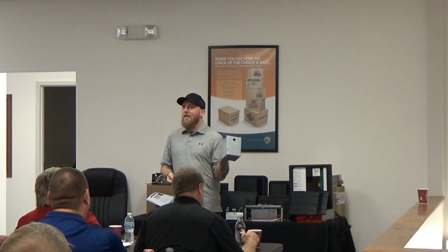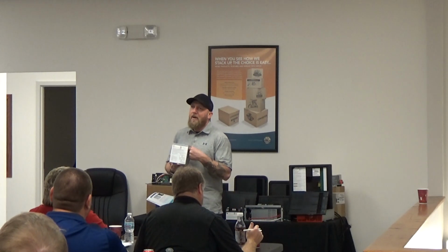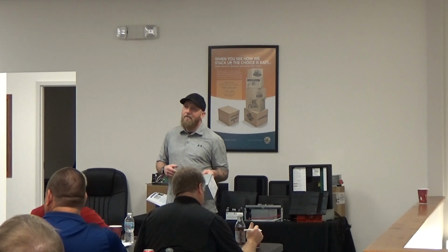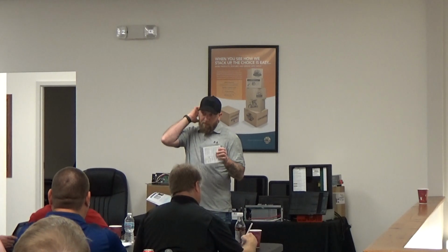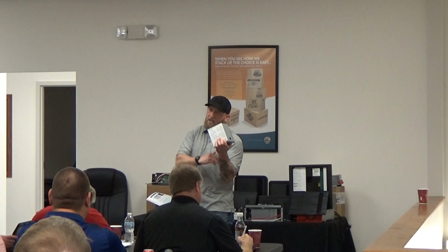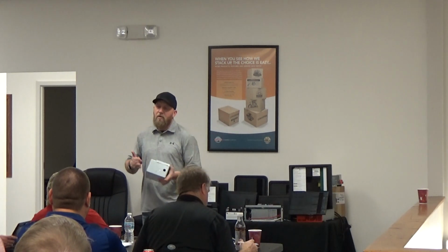Did you say yesterday there's not really anything that could go wrong with this? No, he didn't say that—there are things that can go wrong with it. It has an AC fuse on the timing board, so if you put too high a voltage in there, it can still blow the fuse and then it won't have a time delay. It's basically just a fuse though. And then the sled itself—vibration can offset the sled. The worst thing is when they're switching generator with loads: they can weld the relay. If there's a significant load and they plug in and the relay arcs over, it can weld and stick to one side, so it'll only work off shore power or only off generator, not both.